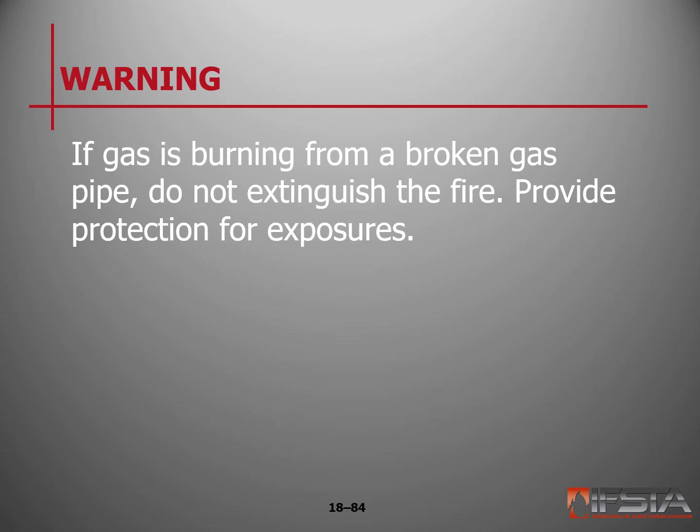Again, if gas is burning from a broken gas pipe, do not extinguish the fire. Provide protection for the exposures. The utility company can block off and turn the gas off.